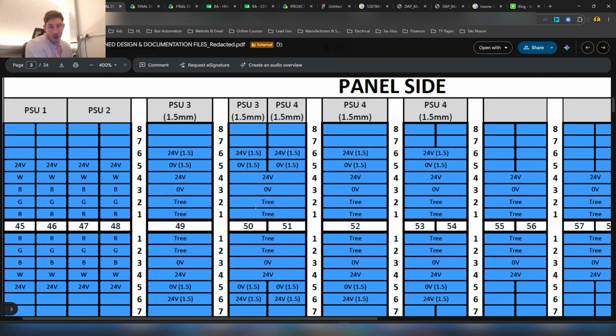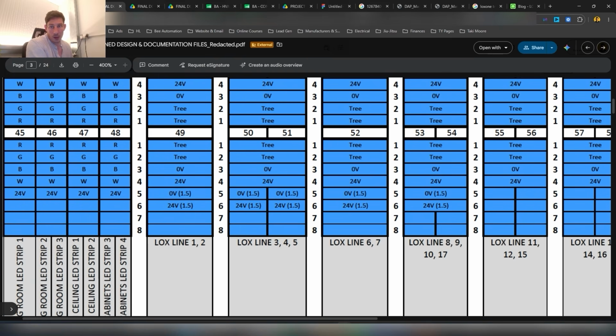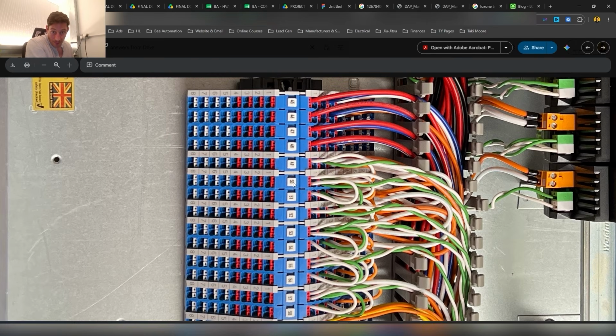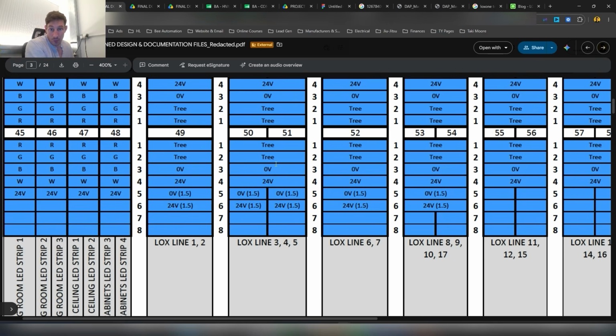What we're doing differently on 50 and 51: we're looping the tree comms. So we got the feed coming in here from the tree extension, and then we're looping into this next terminal block 51, and that carries that same tree comms across all 4 of these terminal points. And we're doing the same with the green, and then we're doing the same with the peripheral 0 volts and 24 volts.